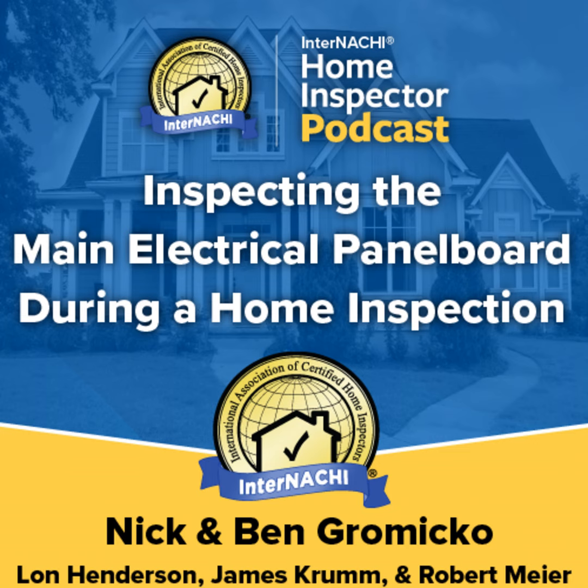The type of arc fault circuit interrupter, AFCI, device currently required by the IRC and NEC is the combination type. This circuit breaker type of AFCI that mounts in the panel board at the beginning of the branch circuit or feeder provides protection for the entire branch circuit or feeder. The AFCI device consists of a standard circuit breaker with additional electronic circuitry that is capable of recognizing the unique current fluctuations that result from an arcing condition.